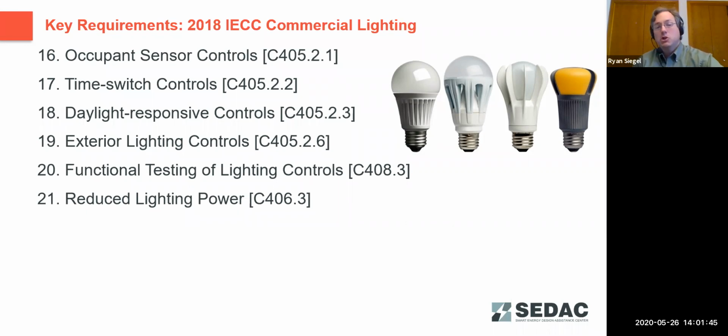So the load may change over time. And so the new unit may in fact be larger than the existing unit. That is possible. Frequently it is smaller, but just a like-for-like replacement, you do have to verify that the new one is correct.